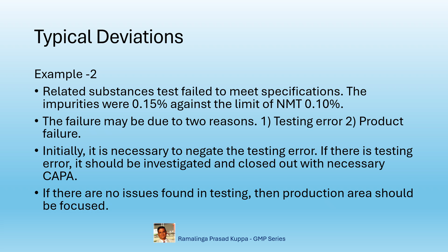The investigation should focus on the instrument. Mostly it may be HPLC that was used for testing. So coming back to QC investigation, in most of the cases where the failure was on the related substances test, the testing equipment will be HPLC. So the focus should be on the HPLC testing procedure. Following should be checked and recorded with detailed description.